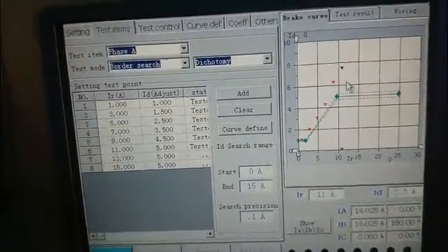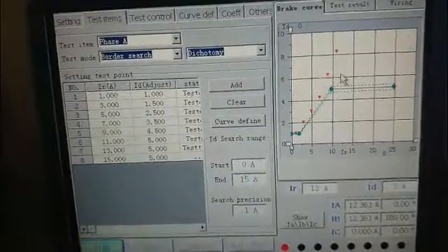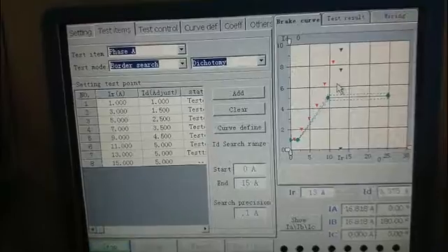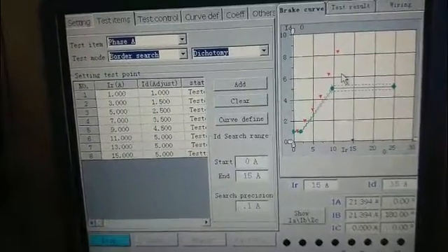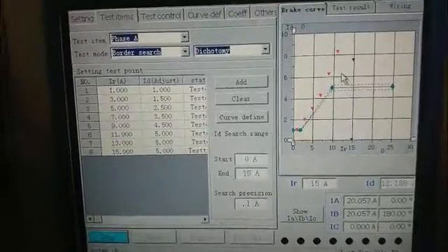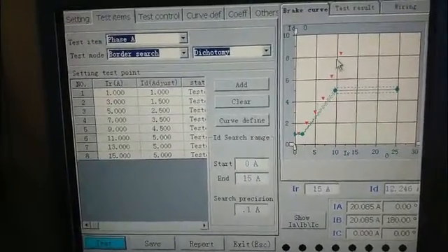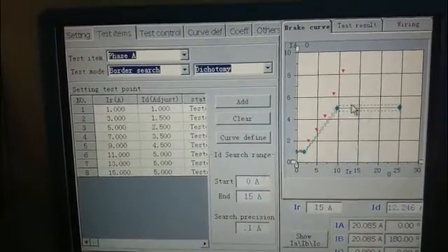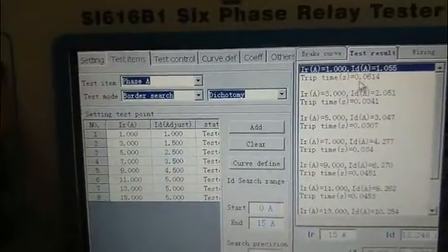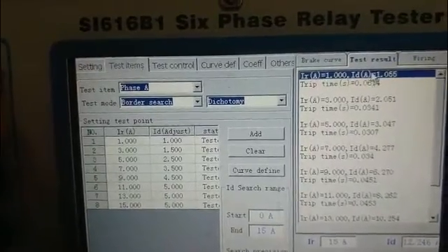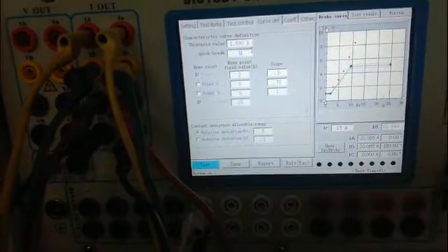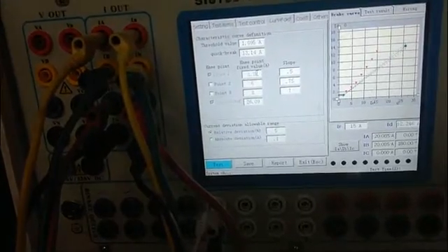We can see the test point does not in this curve the device set before. Then we can look up the test result to see the exact value of the current and the time. Then we can set the curve exactly. We input the exact value as we know.